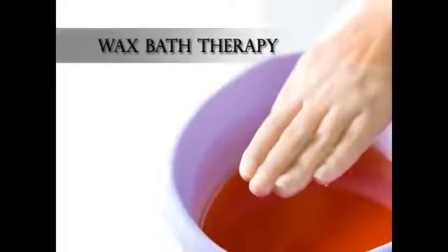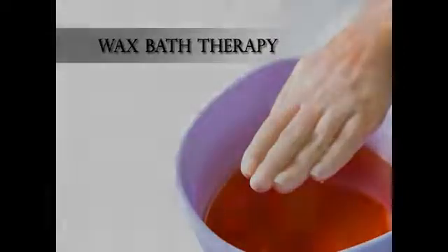And the next topic comes wax bath therapy. The paraffin wax melts at around 54 degrees Celsius, but this point can be lowered by addition of mineral oil such as liquid paraffin. Most wax baths are kept at temperature between 42 to 52 degrees Celsius, often at a higher range for hand treatment and rather lower for the feet. The wax is maintained molten in stainless steel or enameled bath, which are electrically heated. Temperature is kept constant by the thermostat.